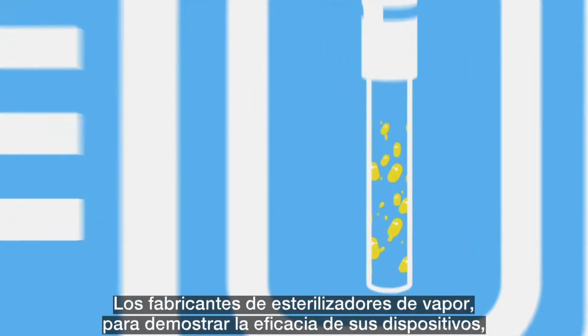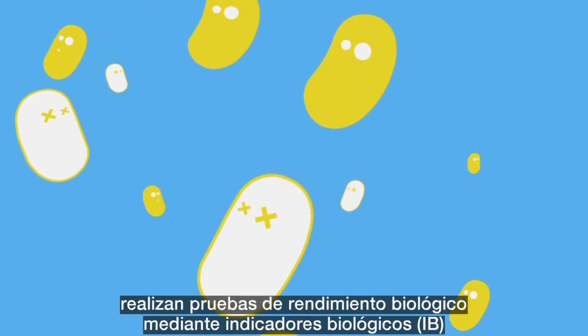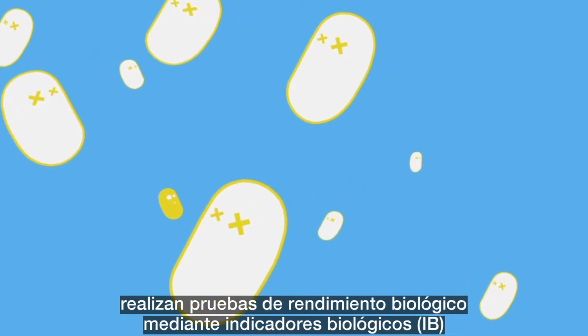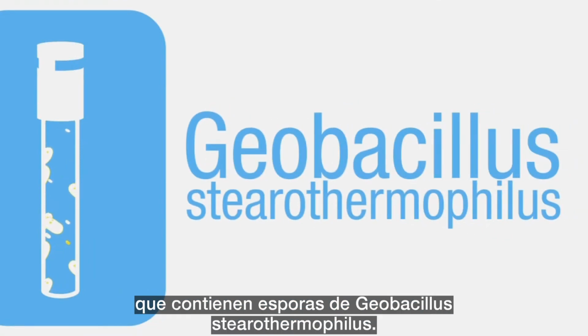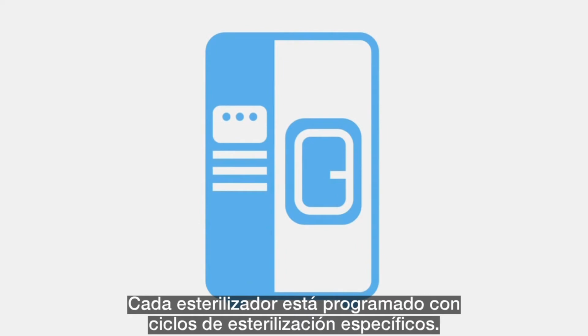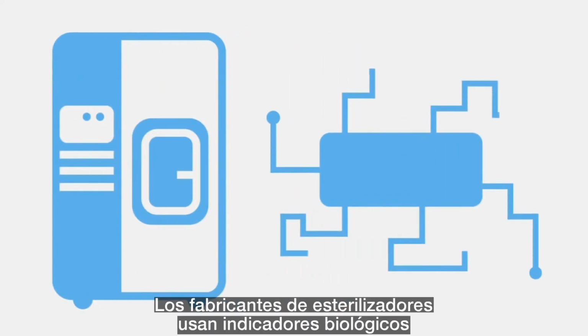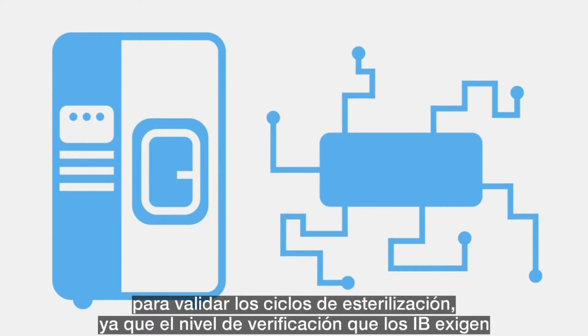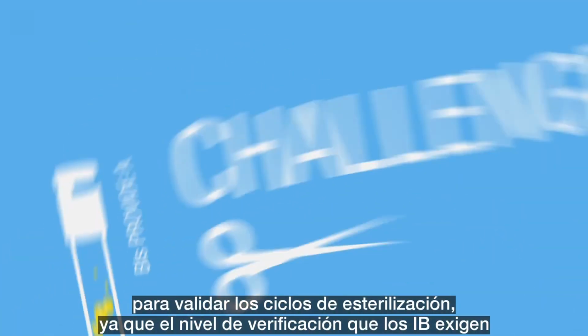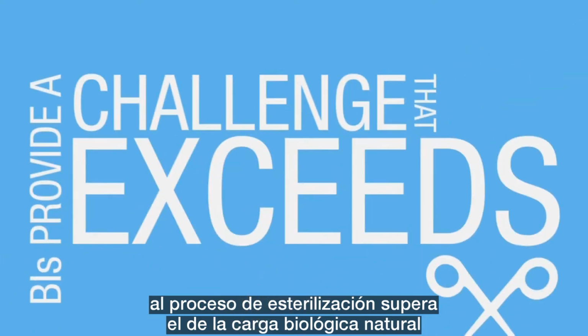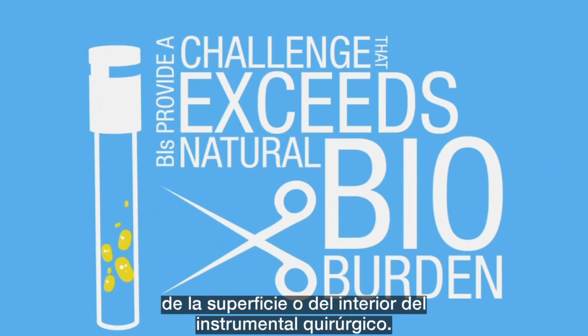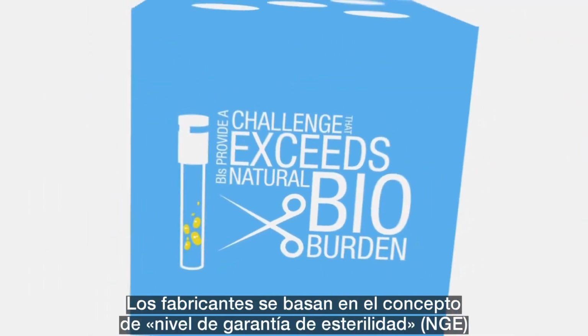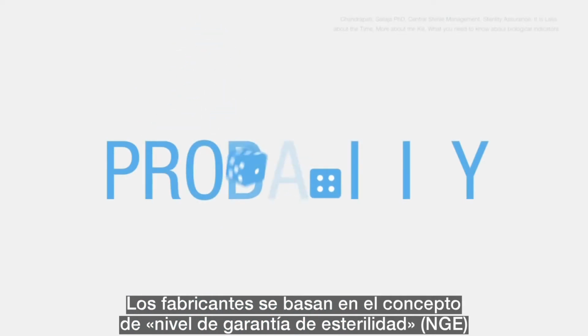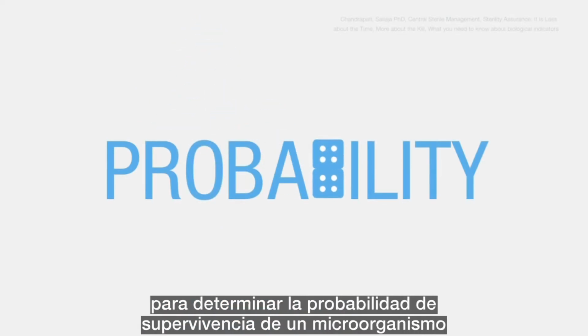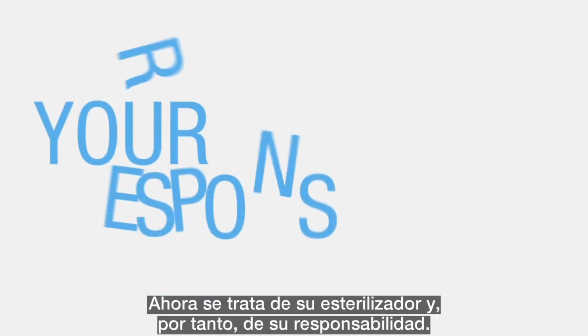The steam sterilizer manufacturer demonstrates efficacy with biological performance tests using biological indicators, BIs, containing Geobacillus stearothermophilus spores. Your sterilizer has specific sterilization cycles programmed into it. Sterilizer manufacturers use biological indicators to validate sterilization cycles because BIs provide a challenge to the sterilization process that exceeds the challenge of the natural bioburden in or on surgical instruments. Manufacturers rely on the concept of SAL, sterility assurance level, to define the probability of a surviving organism for a validated sterilization process. And now it is your sterilizer and therefore your responsibility.